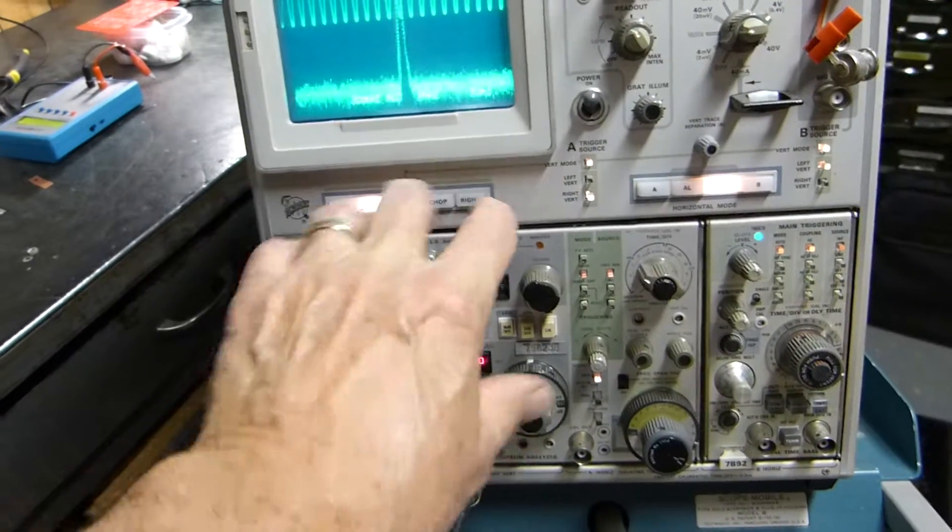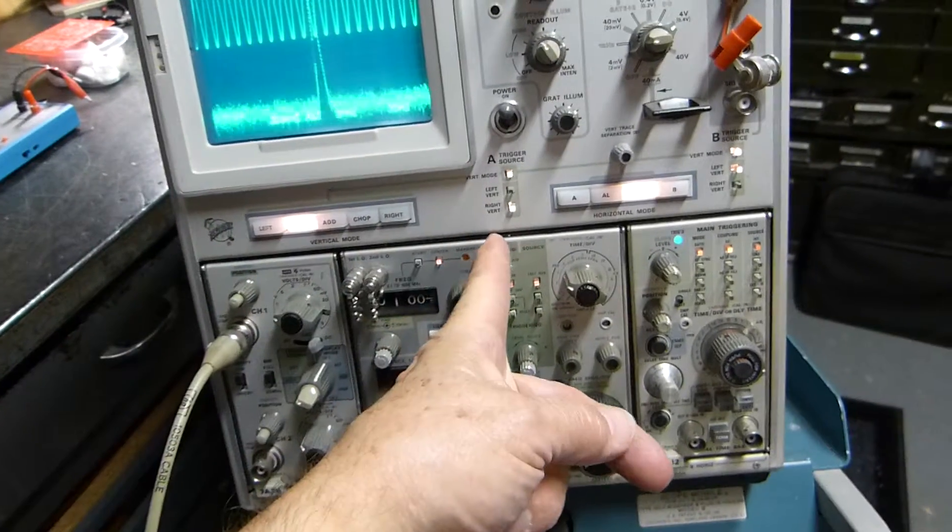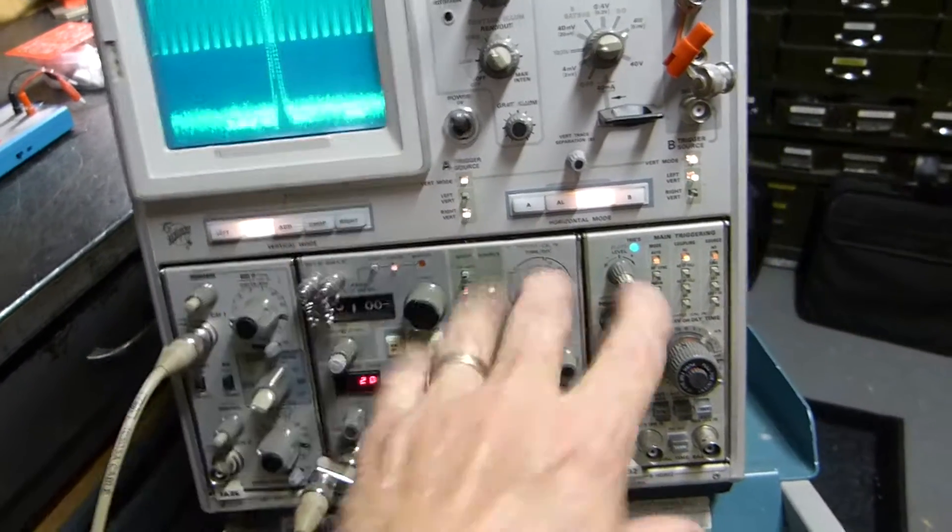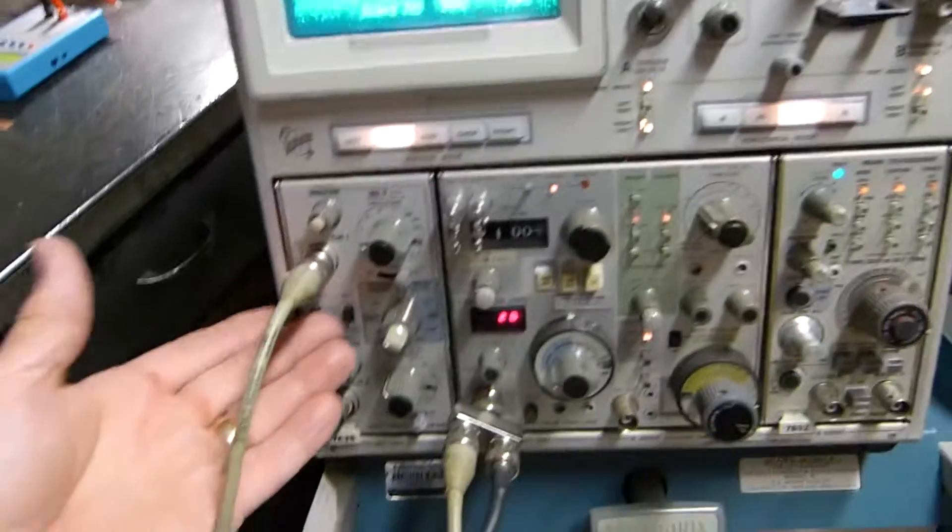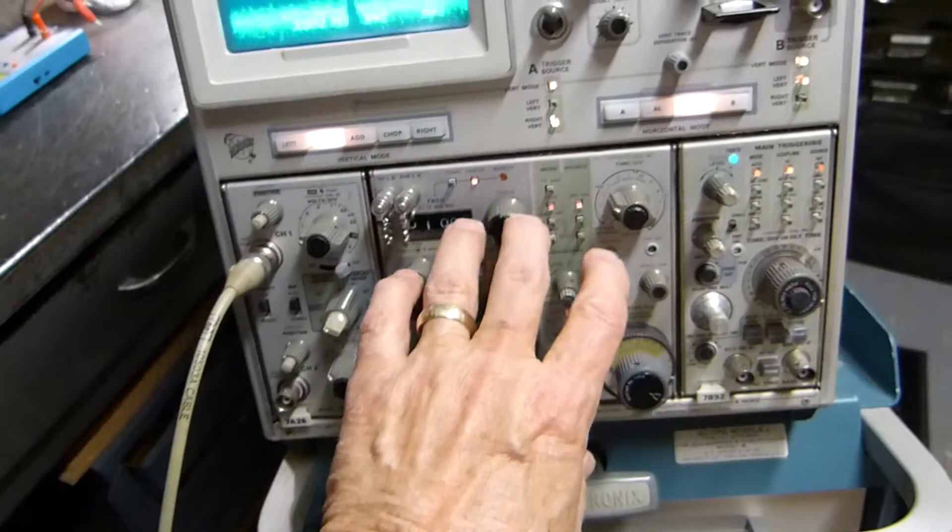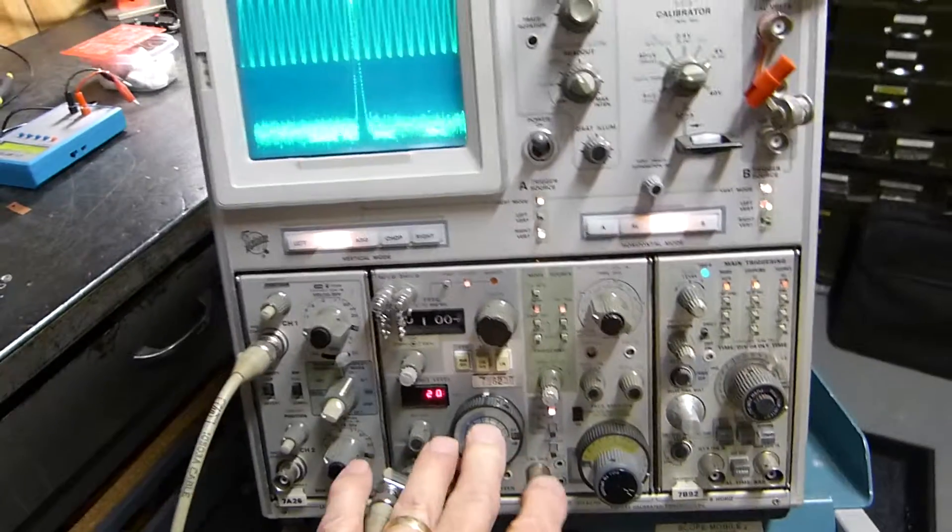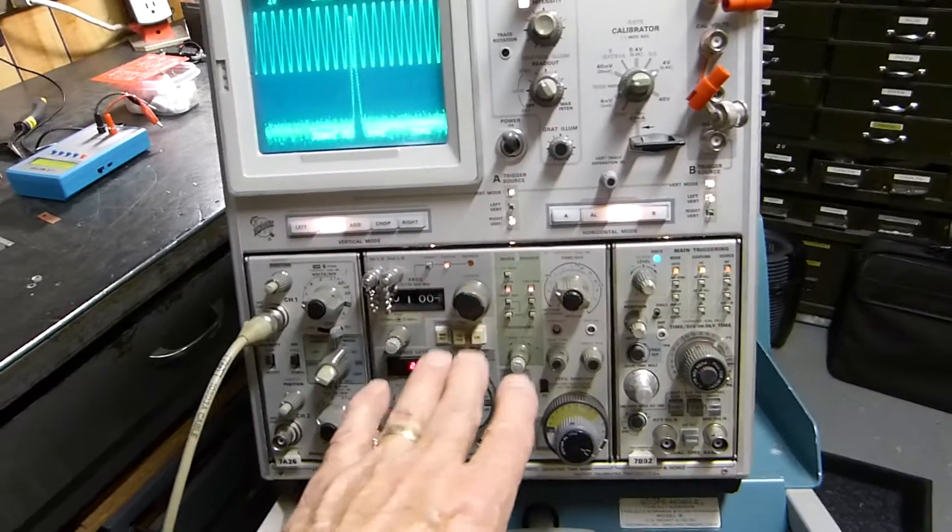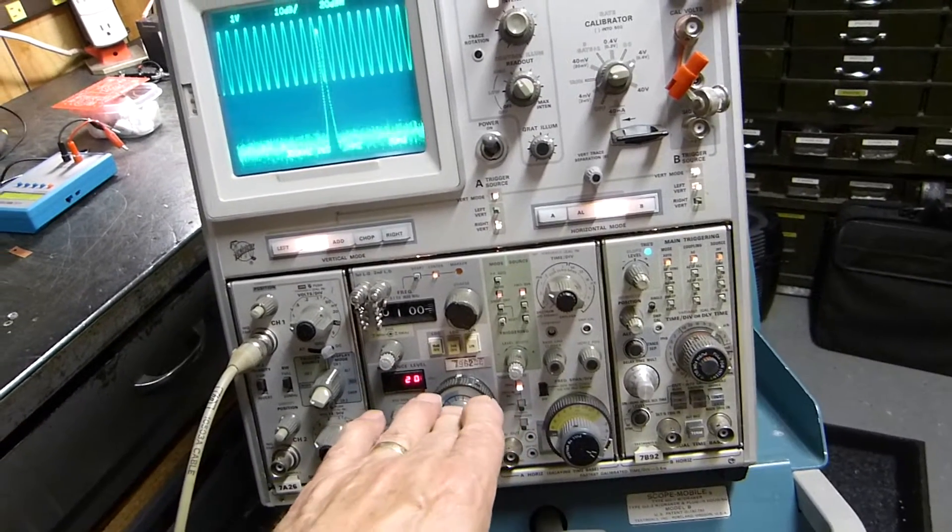These two slots right here, I've made some videos on this oscilloscope before. This slot and this slot are vertical slots, and this slot and this slot are horizontal slots. Well here's a vertical amplifier and here's a spectrum analyzer. They make three spectrum analyzers for this 7000 series: a 7L5, a 7L12, which is what this is, and a 7L18 I believe.